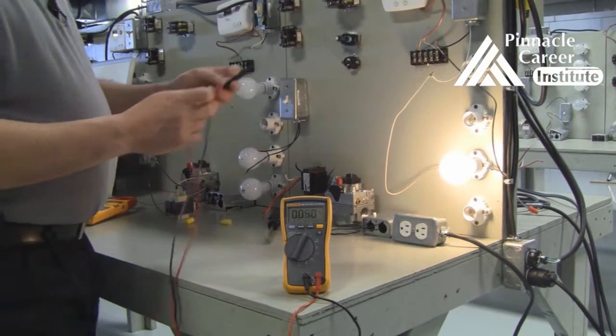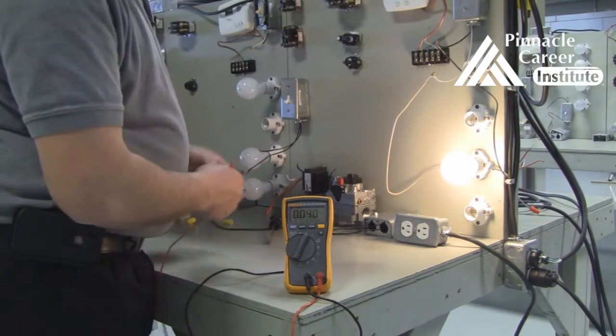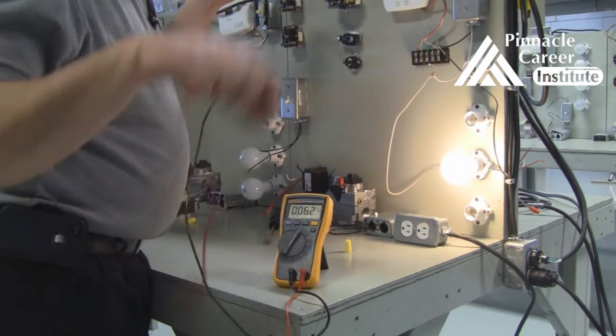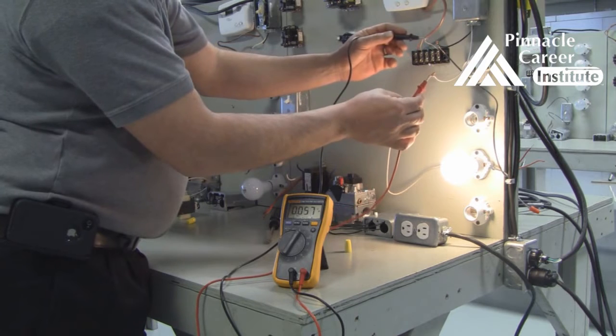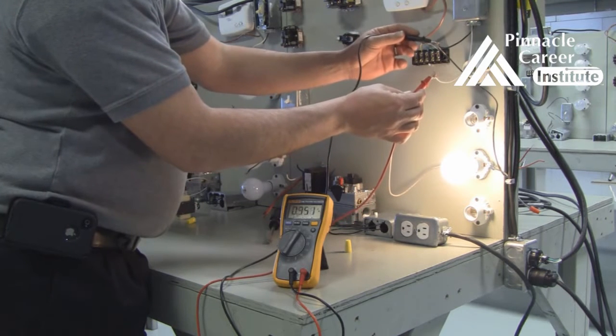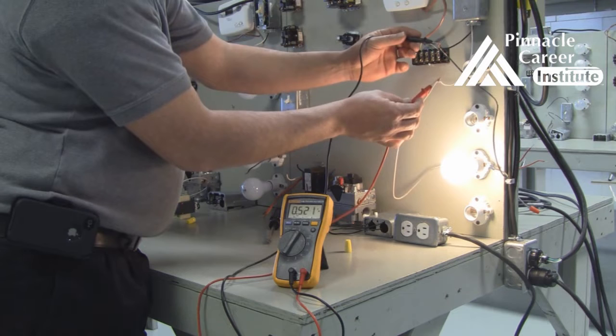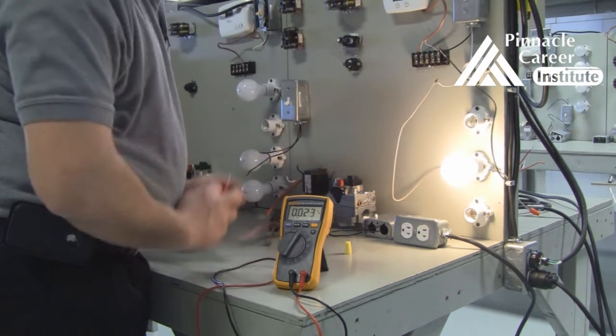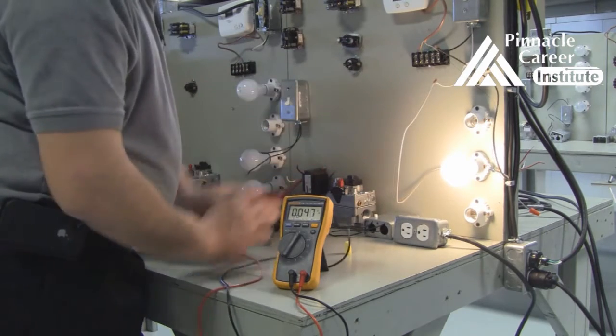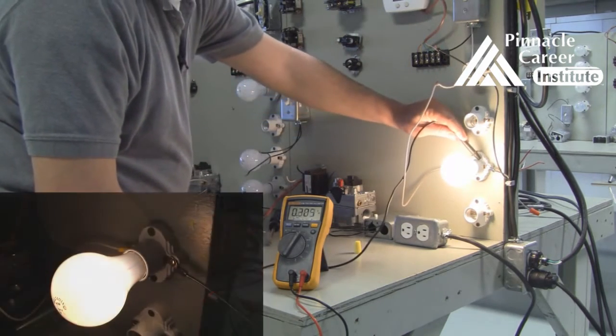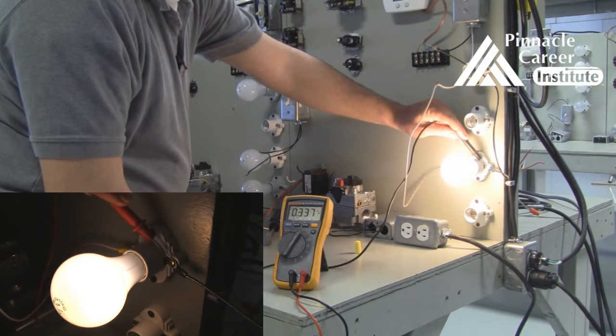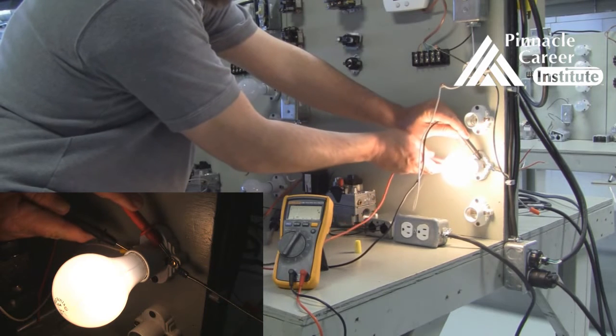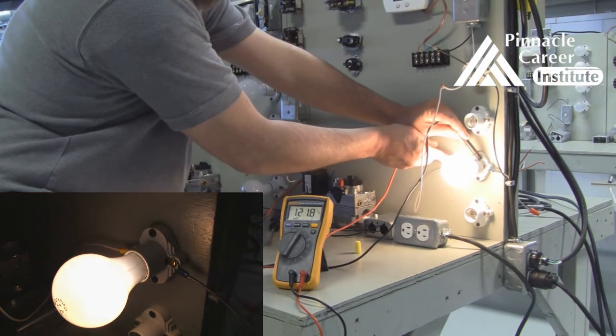Okay, now we're going to test bare wires that you would see from inside the wire nuts as we take the wire nut off. Now, you're going to test, once again, the neutral and the 120 or the hot wire, the black wire in this case. And here we're getting 120 volts. Now, that's the same. You can see the light bulb is on. And if I place a meter lead on the wire coming into the light bulb on one side and then the neutral, you'll see 120 volts there.